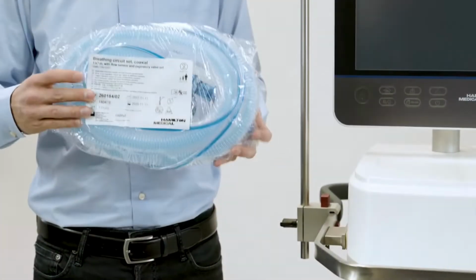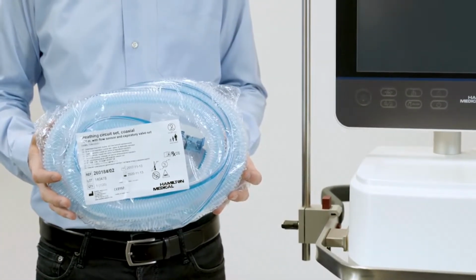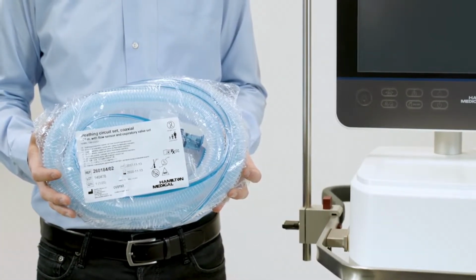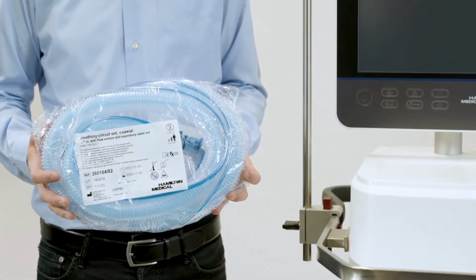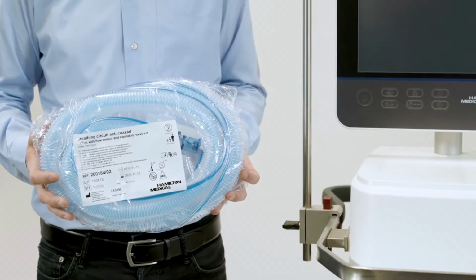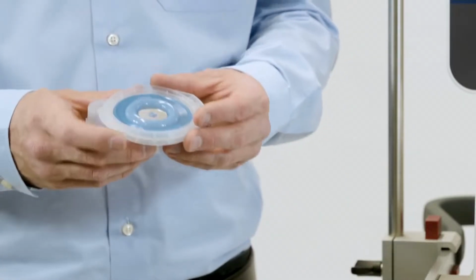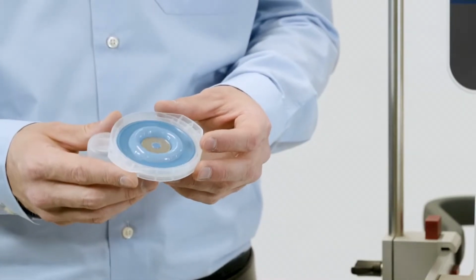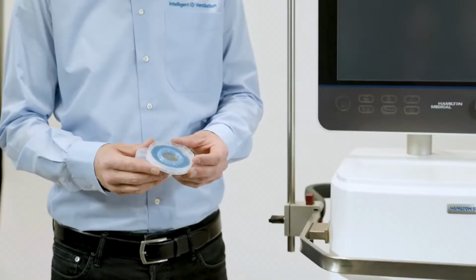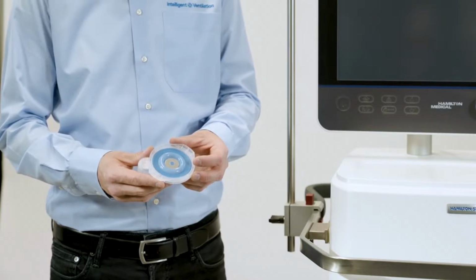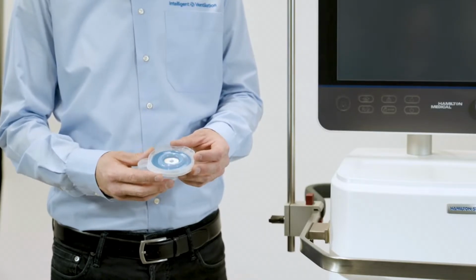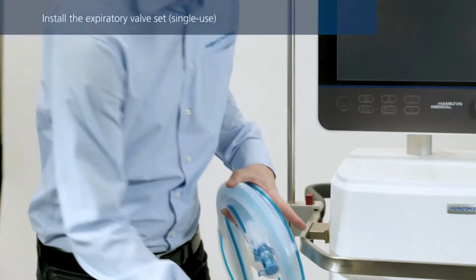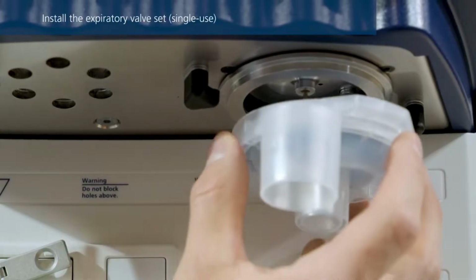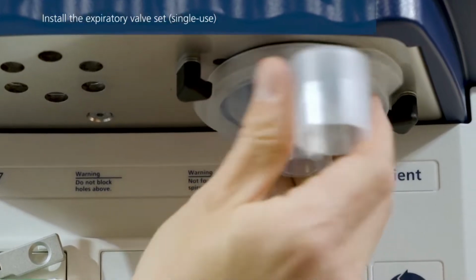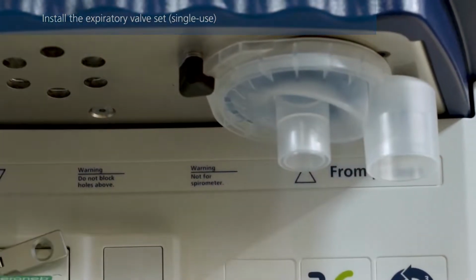If you are using a pre-assembled coaxial breathing set, this contains everything you need: the expiratory valve set, the breathing circuit, and the flow sensor. In a single-use expiratory valve set, the membrane is permanently attached to the expiratory valve body. Do not remove, tug, or pull on the membrane. Position the expiratory valve set in the expiratory port and twist it clockwise until it locks into place.